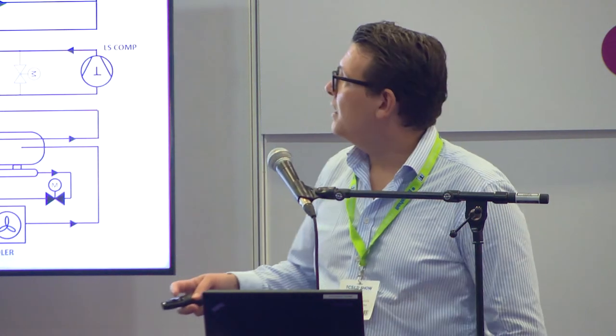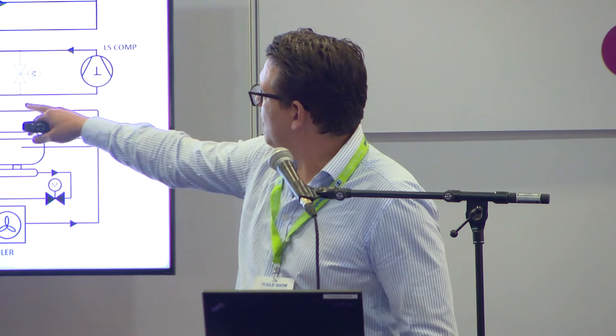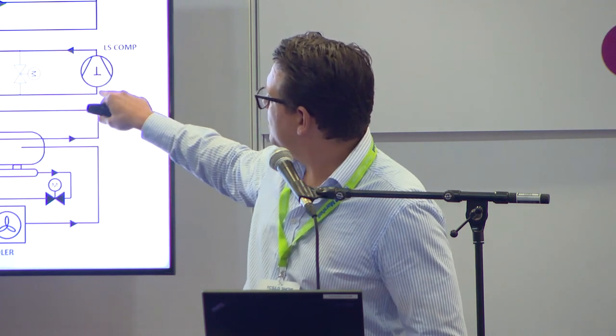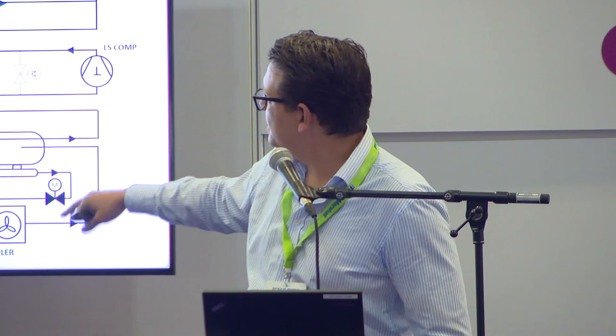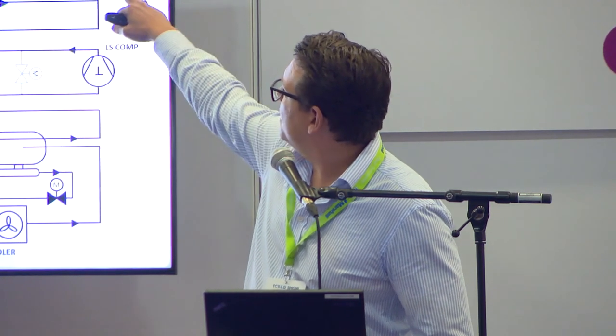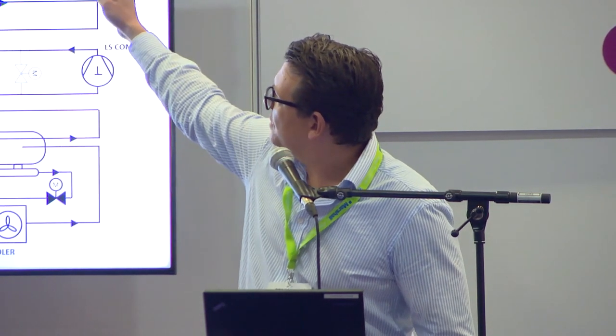The next case study I'm looking at is a two-stage transcritical CO2 system. This is for a production facility looking at pizzas. Again, similar concept at the bottom over here, but because we're looking at quite a large pressure difference between our evaporating pressure and our gas cooler pressure, we have two stages. We have a compressor over here which increases the pressure from the low side to an intermediate pressure, which then the high stage compressor pushes through the gas cooler and into the interstage vessel.